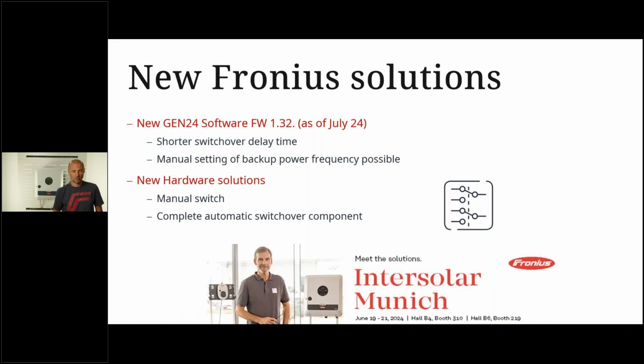Now, some news from Fronius. We get a new software end of June, beginning of July, firmware 1.32, with which we have reduced the switchover delay time to about 15 seconds. And also the manual setting of backup power frequency is possible now. So we can reduce the 53 Hertz to, for example, 51 Hertz. If you have any load which is not working correctly with the 53 Hertz, then you are able with this software to manually set another frequency between 50 and 53 Hertz. So that can be adjusted.